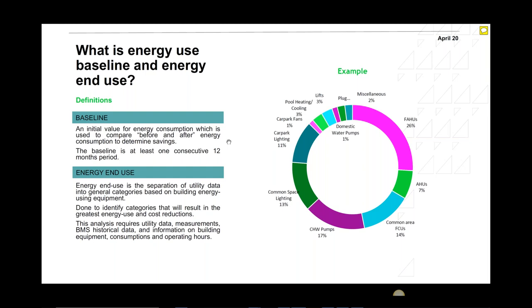So this is showing here the kilowatt hours, or the electrical consumption, of the different components of the building. There would be another component, which is the district cooling, which is not shown here, which would normally be in kilowatt hours or ton hours. So thank you very much for voting. The correct answer is district cooling, mainly because I don't see any chillers, but I see cooling and chilled water pumps. Looking at this end use analysis, you can see that the FAHUs, or outside air handling units, and fan coil units are the highest consumers, chilled water pumps also high, and the lighting.